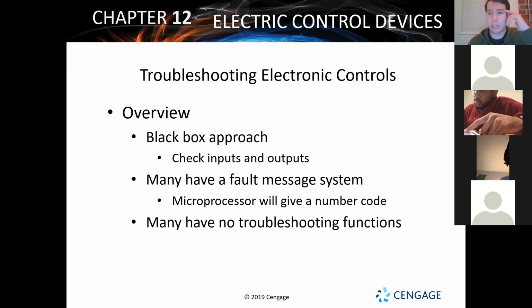So I talked early at the beginning about a way to troubleshoot these electronic controls. The main one is the black box approach. Check and make sure you've got high voltage coming in, make sure you've got low voltage coming in, and look at your wiring, look at your board, figure out where that voltage is supposed to be going, and see if it does. If the voltage comes into the board and it's not leaving the board and the board's not sending it anywhere, the board is probably your issue. Other things you're going to look for is easy stuff, like any burnt or charred thermoplastic or section of the control board. If there are any resistors that are burned up or anything like that, that's going to be a big issue, and you're going to want to get a new board.